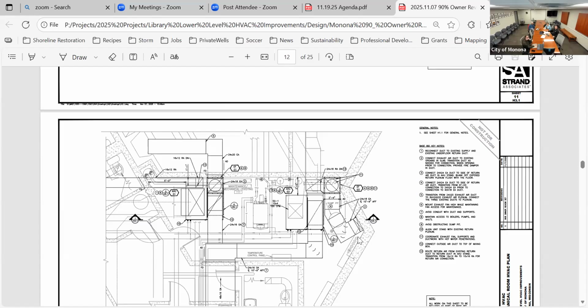There is a combustion air intake that goes through the ceiling out to the front of the building. If you've ever seen, there's a couple of fins on the front of the building right here. That's part of this air intake system. This is currently not ducted into the system. It just goes through a hole in the ceiling. That's a rough cut piece of concrete that they basically jackhammered out of the ceiling. And so technically it's exposed to the outside directly, which is not good, obviously, for a lot of different reasons. So that's going to actually get hard ducted in.